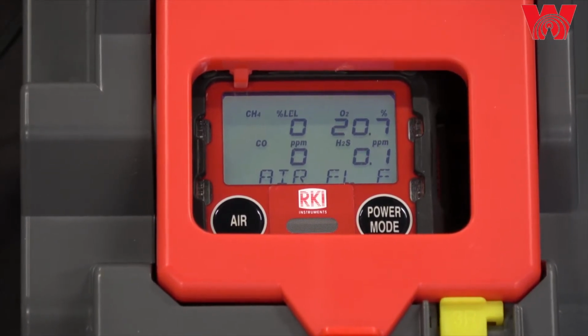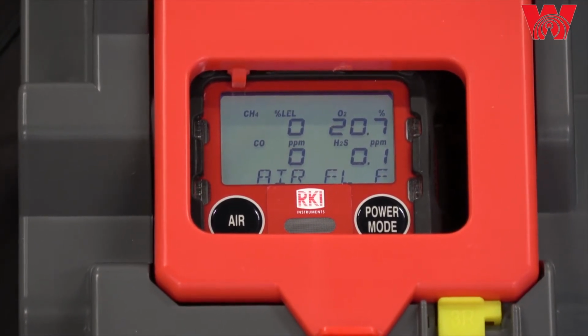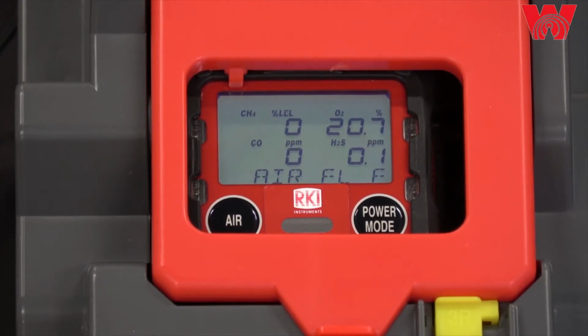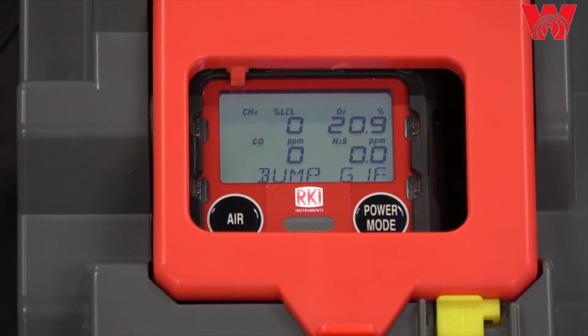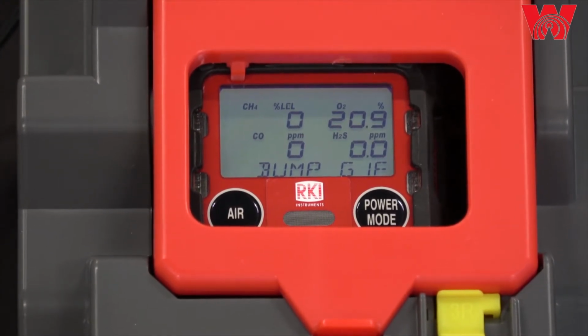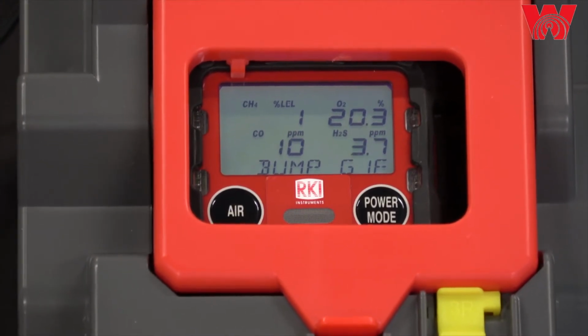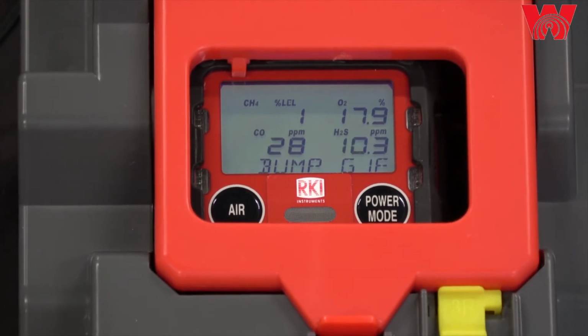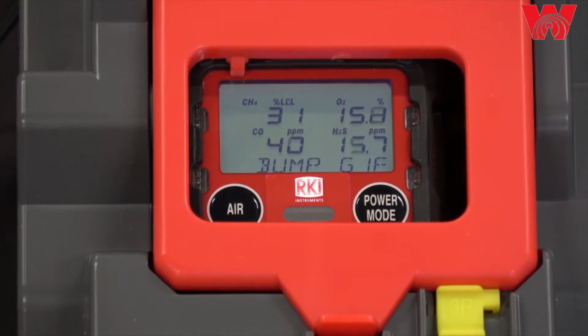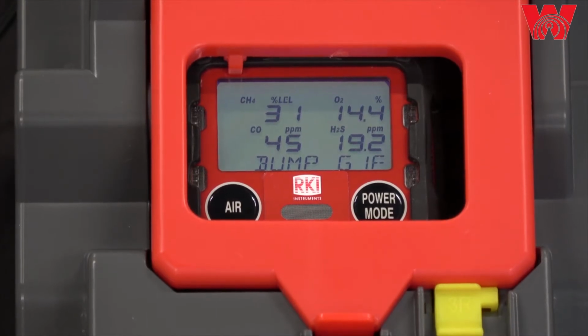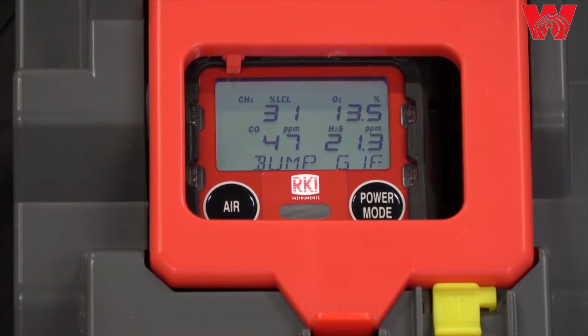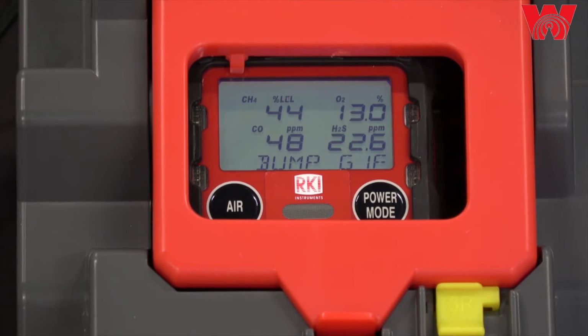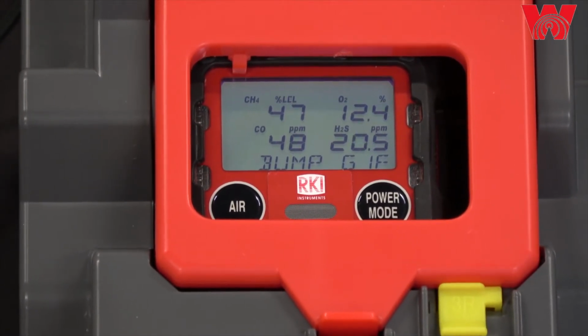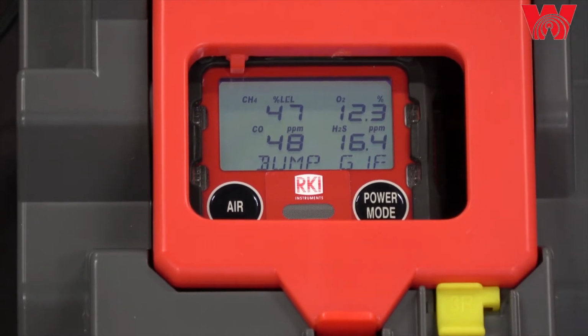And if those readings fall within the tolerance for the bump test, it will pass the bump test and move on. Using fast bump is a way to save calibration gas. So now we have calibration gas flowing. You can hear the pump running. And now you hear the pump stop. The gas is still sitting up against the GX3R, and you can see the readings are still changing.